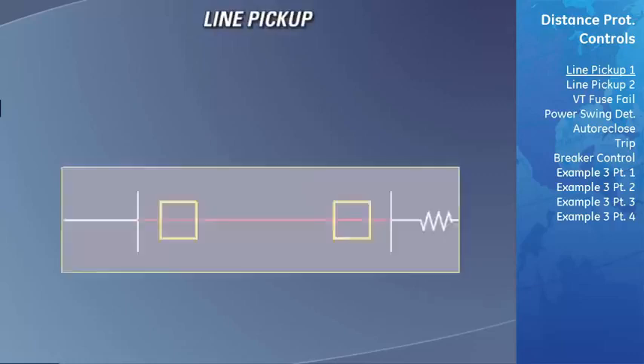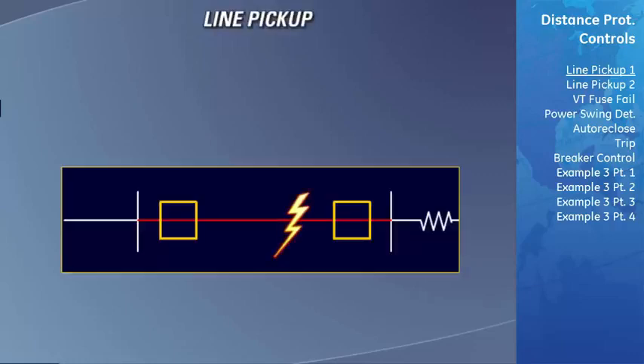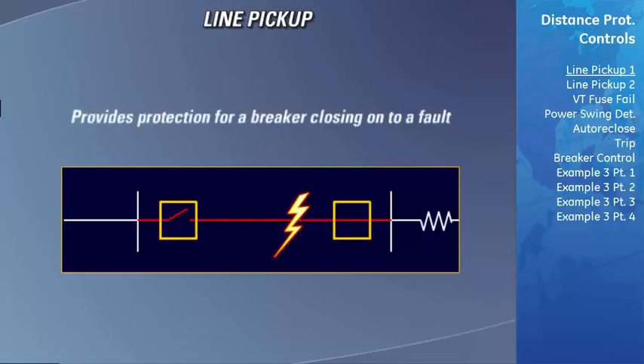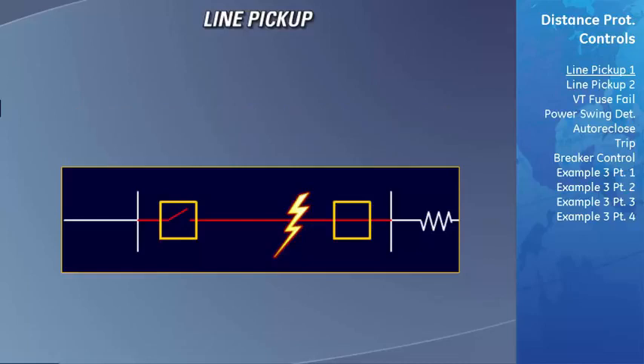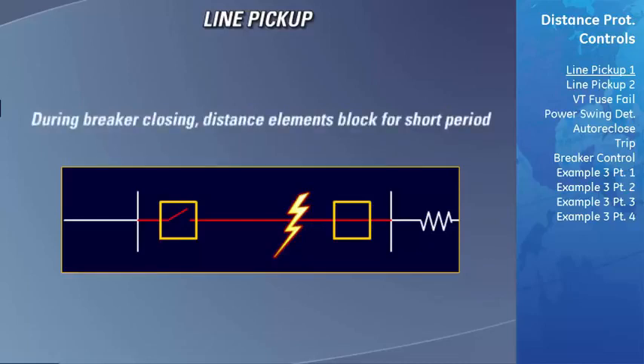The line pickup element that is available in the D60 is an additional protection feature that provides fast tripping of a breaker for instances where a breaker is closed onto a fault. It is also referred to as the switch onto fault function. The operation of all distance elements is blocked for a brief period after the energizing of a breaker is detected to avoid a race condition that can occur as the voltage and current builds up from a zero level to their steady states. During this period, the line pickup element will protect the transmission line.